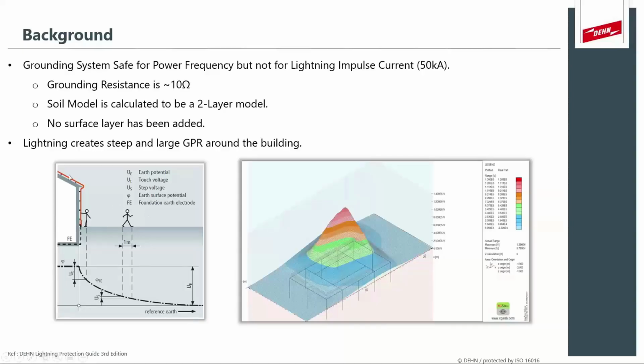Now, the steepness that we described earlier, due to lightning current, is not necessarily such a big hazard within the building, but around the building outside, where people would walk, especially walkways and things like that. So we also need to address the very high peak current, or the peak steepness of the ground potential rise, around the building as well. And when people touch parts of the lightning protection system, it will be connected to the grounding system, and there is also the step voltage. People would walk around the building based on a 1 meter spacing between their feet.